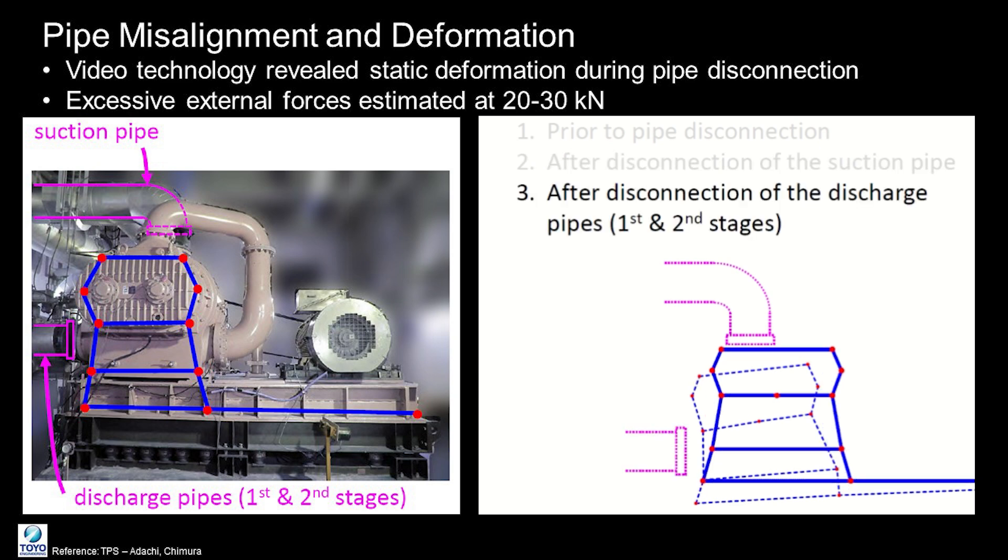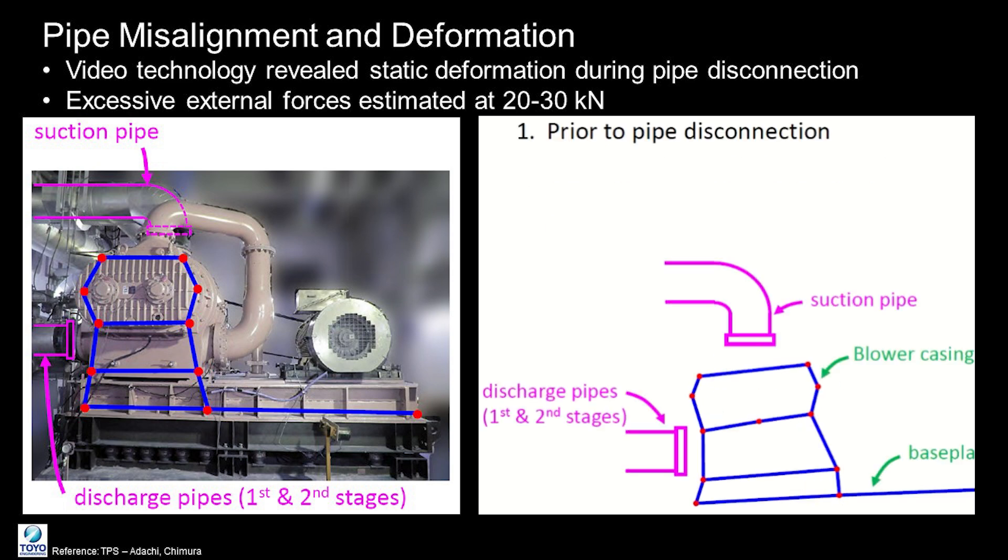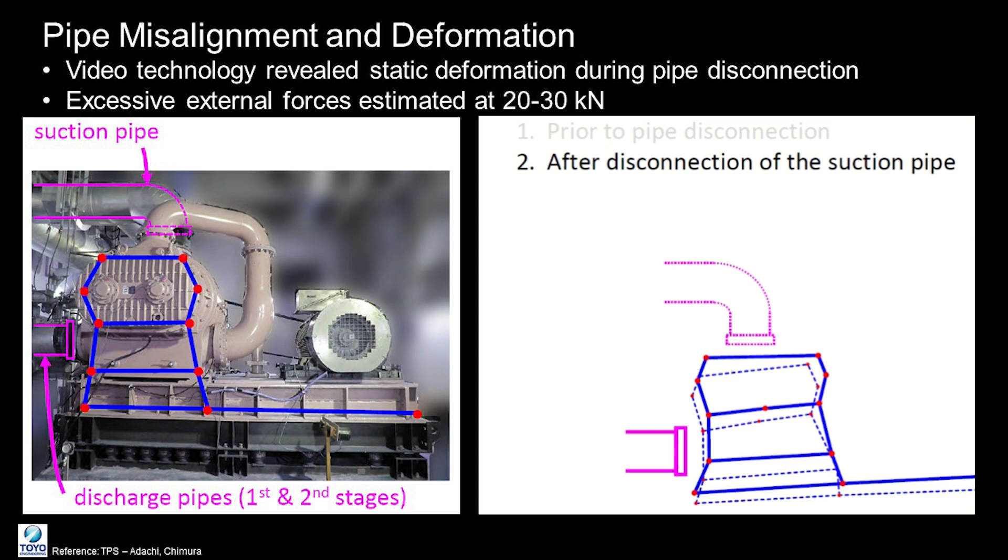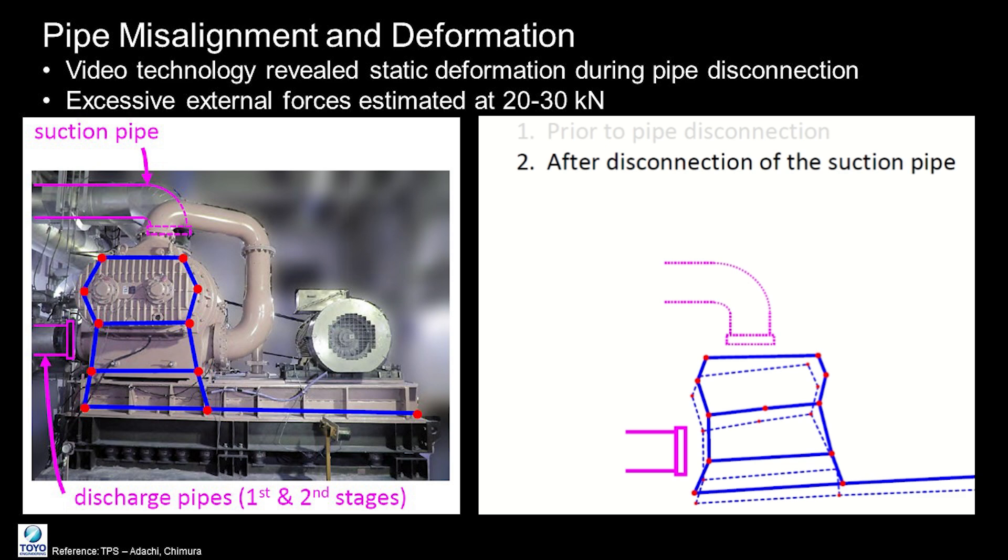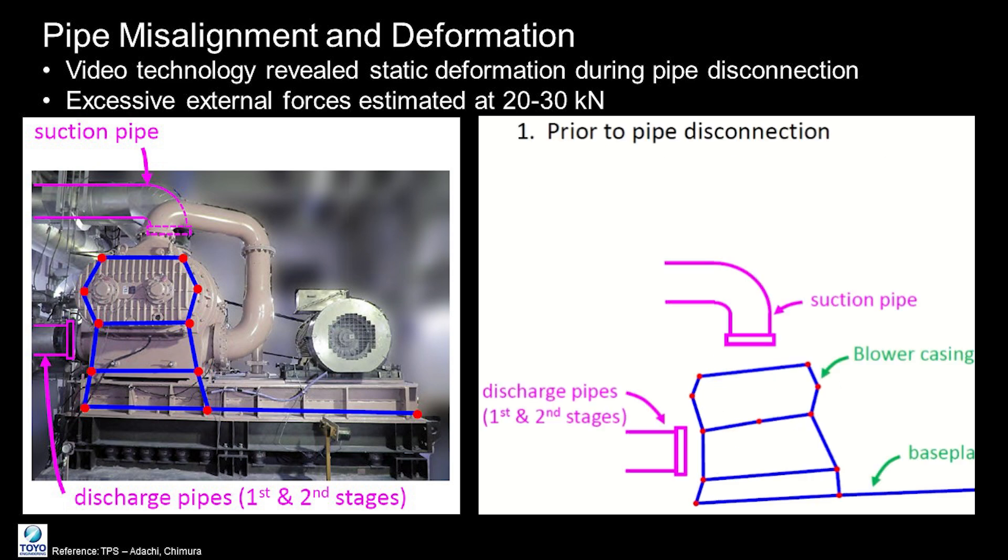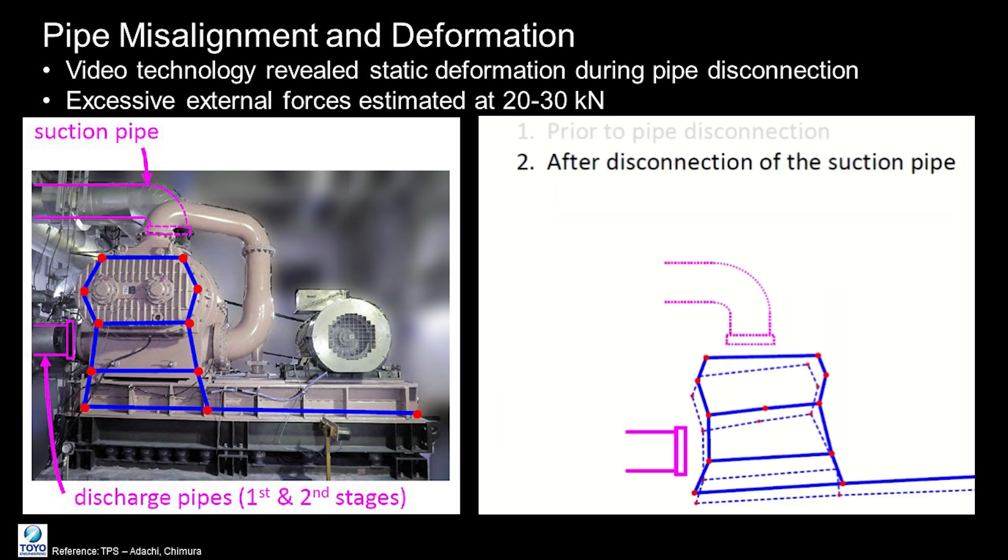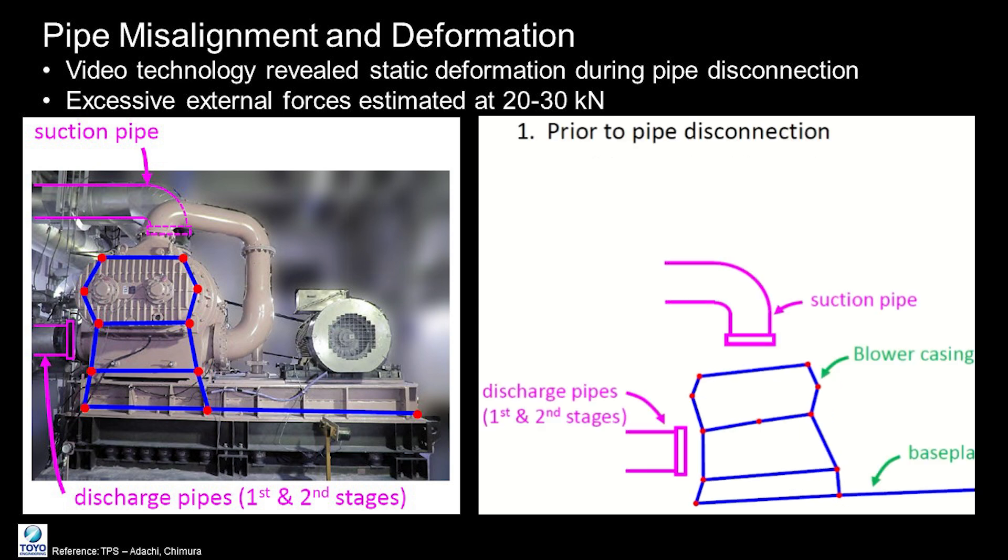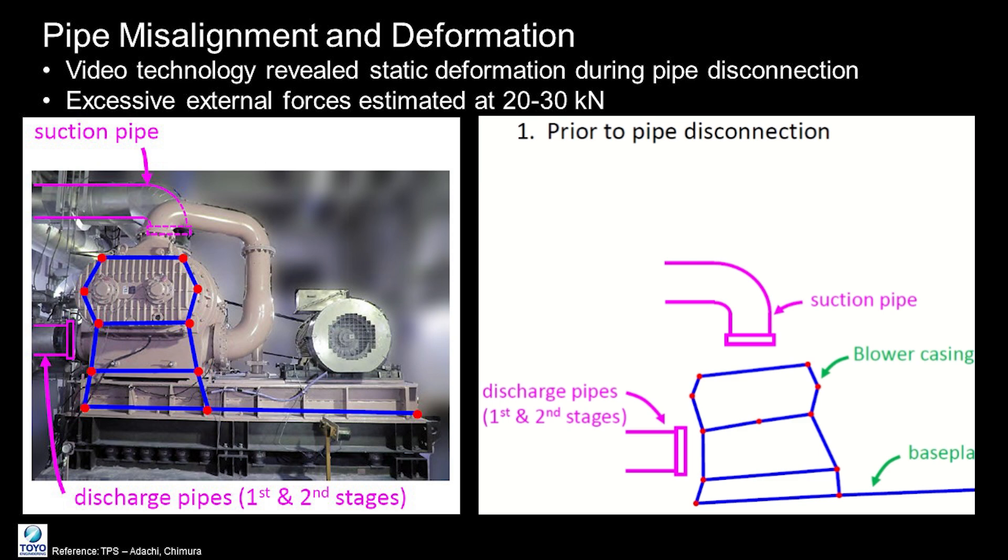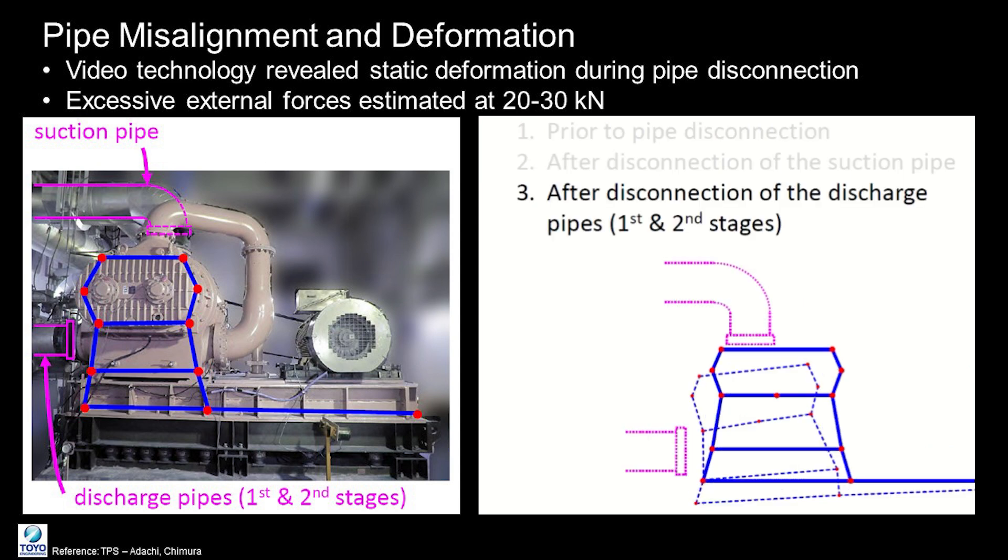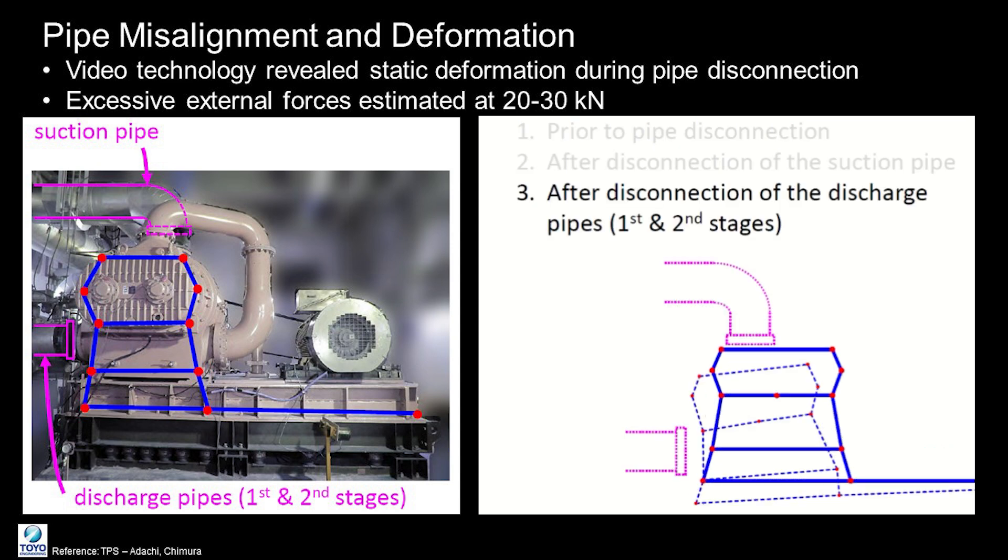Alongside structural resonance, it was also suspected that excessive excitation was contributing to the vibration issues. Video-based motion enhancement technology was used to visualize the deformation of the blower casing caused by misaligned pipes. This external force was found to largely affect both the 46 Hz and 93 Hz vibrations. To confirm the effect of pipe misalignment, the suction and discharge pipes were disconnected one by one. The video-based technology allowed observation of the static deformation of the equipment, confirming that excessive pipe external forces were causing casing vibration.